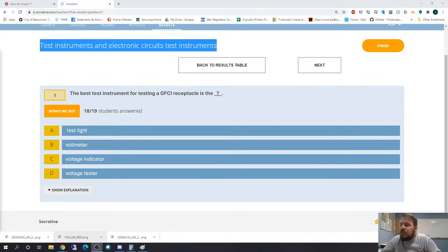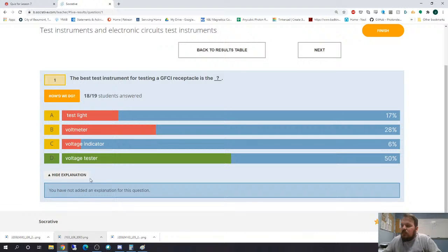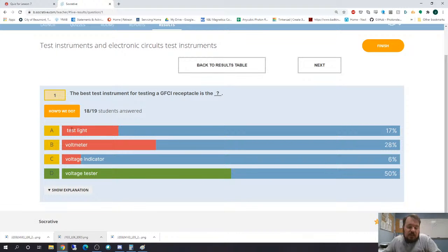The best test instrument for testing a GFCI receptacle is the voltage tester. A test light just has a light - you touch things and it lights up. The voltmeter would probably be my second choice. A voltage indicator only tells you yes or no that there is voltage - a no contact voltage indicator. Widowmakers is another name for them. I'm drawing a blank on the actual term... tic tracer, that's the word.